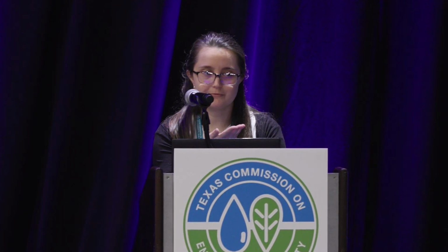Yes, and that is a good point. As I had noted, there were a lot of other rules aside from just the monthly testing under 30% load. One of those other rules is you have to have, I believe, 48 hours' worth of fuel on site wherever you have a generator. And so that plays into you storing this fuel on site for however long until you actually need it. So that's a good point to make sure that it's actually viable fuel that you have on site.